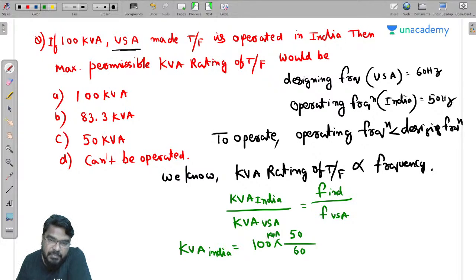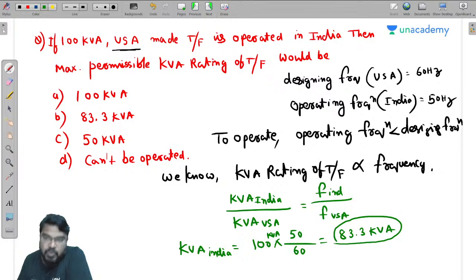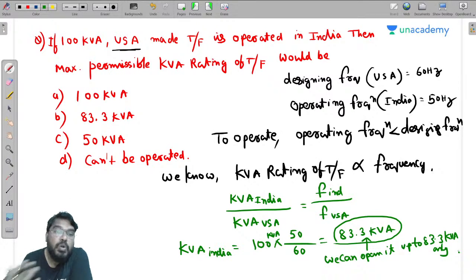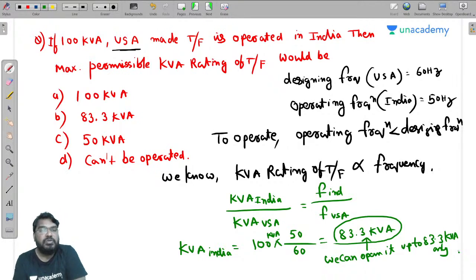100 kVA multiplied by 50 divided by 60, that is equal to 83.3 kVA. So that means we can operate it up to 83.3 kVA only. We cannot operate more than 83.3 kVA. So this is nothing but the maximum permissible kVA rating of the transformer.